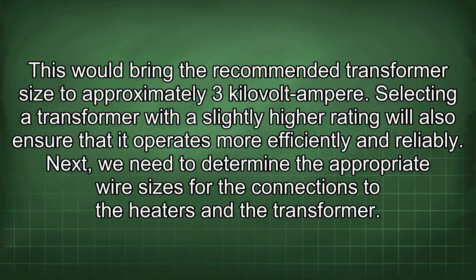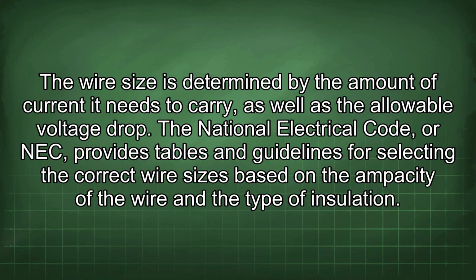Next, we need to determine the appropriate wire sizes for the connections to the heaters and the transformer. The wire size is determined by the amount of current it needs to carry, as well as the allowable voltage drop. The National Electrical Code, or NEC, provides tables and guidelines for selecting the correct wire sizes based on the ampacity of the wire and the type of insulation.